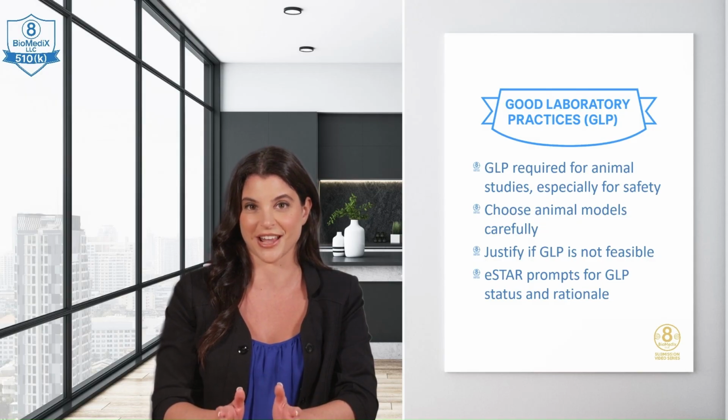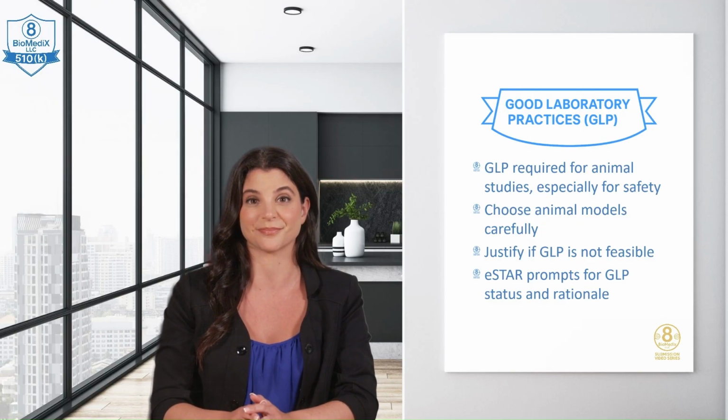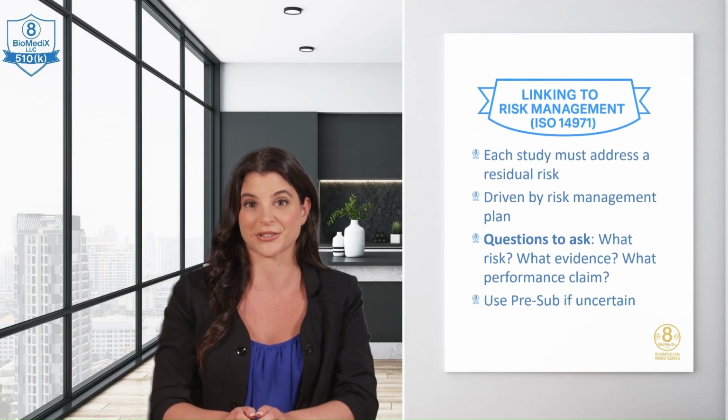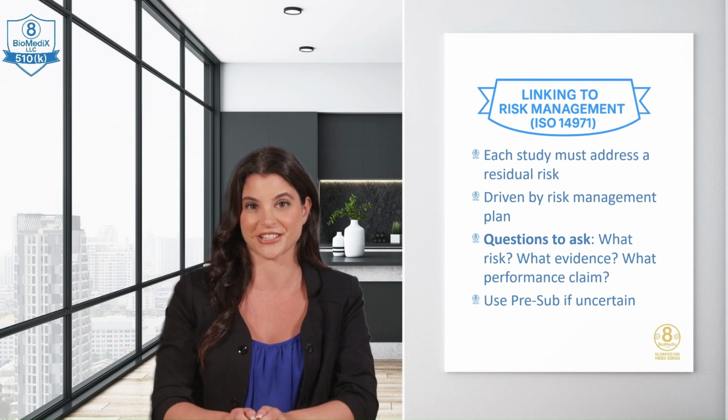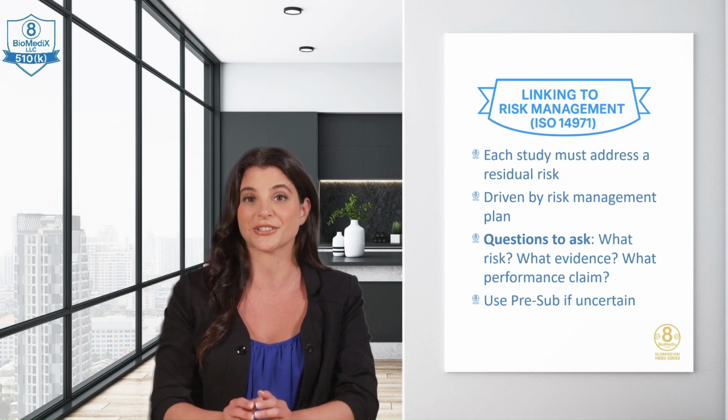Linking to Risk Management, ISO 14971.1. Remember, every clinical or animal test should directly address a residual risk identified in your risk management file. This is where ISO 14971 comes in. Your study must be driven by risk. What risk are you resolving? What evidence will reduce it to an acceptable level? How does this link back to your device's safety and performance claims? If you're unsure whether a study is needed, consider a pre-submission with the FDA. eSTAR includes a pre-sub template that allows you to share your plan early and avoid costly missteps later.